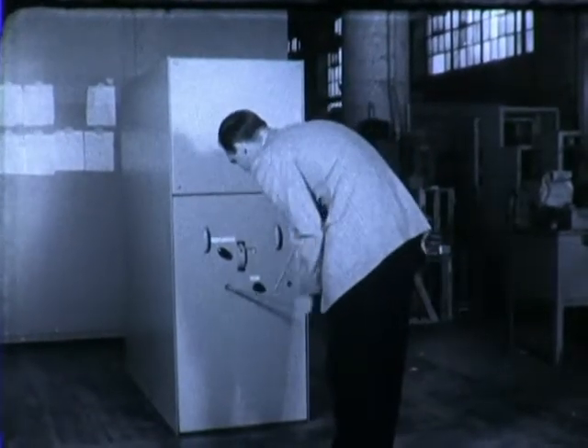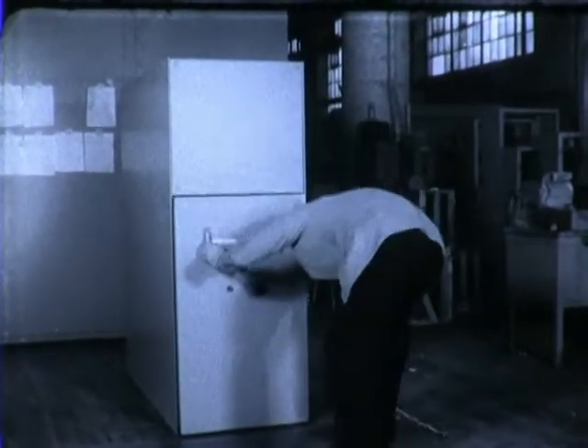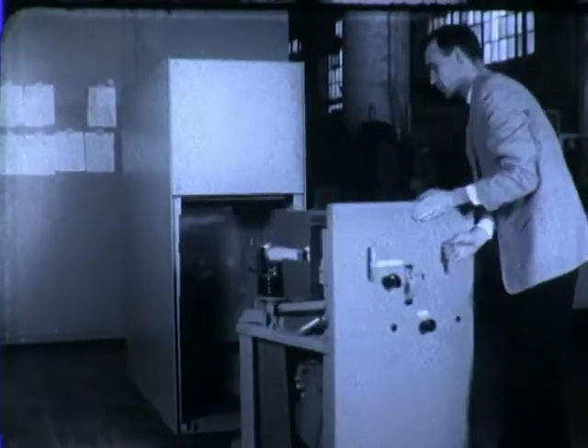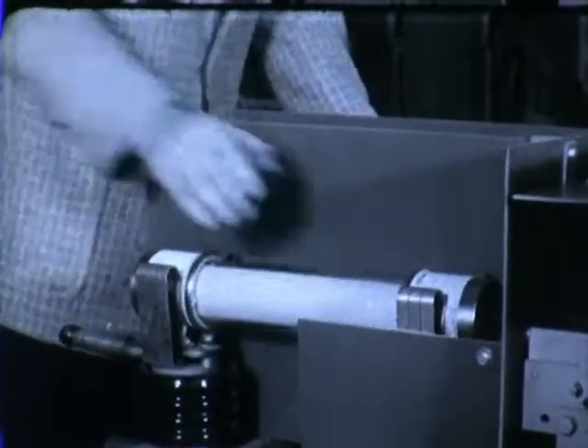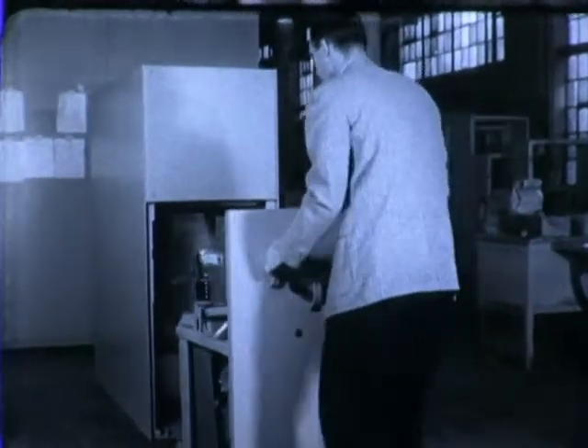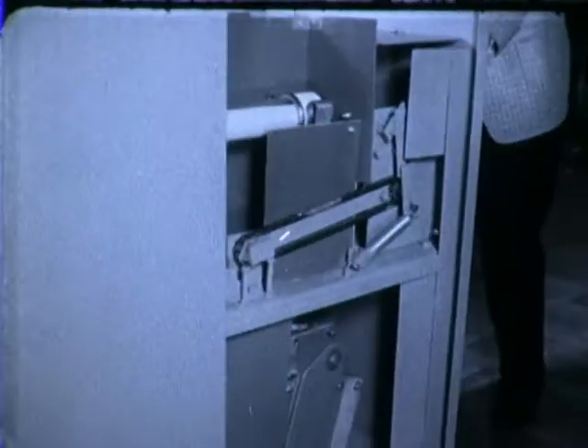The rollout feature of the equipment provides maximum accessibility for inspection and maintenance and maximum safety for operator and equipment. The rollout element, for example, is easy to remove, and fuses are readily accessible for removal or inspection. For operator and equipment safety, all energized parts are completely shielded. For example, a rotary shutter shields the stationary primary contacts, automatically covering them as the rollout element is removed.